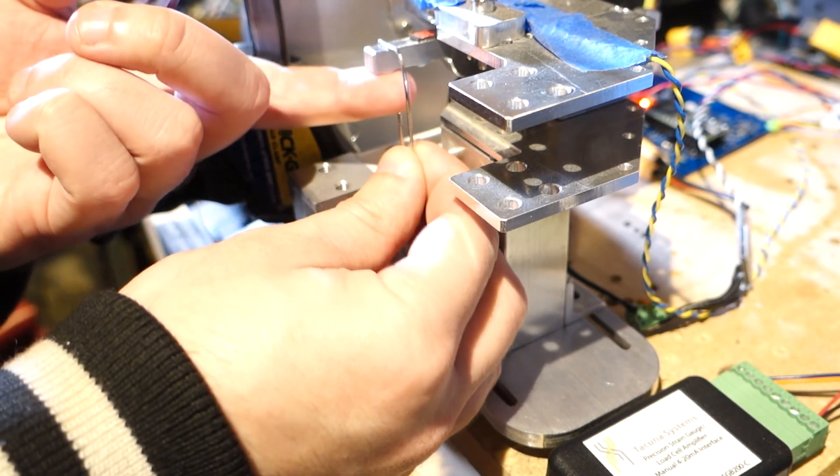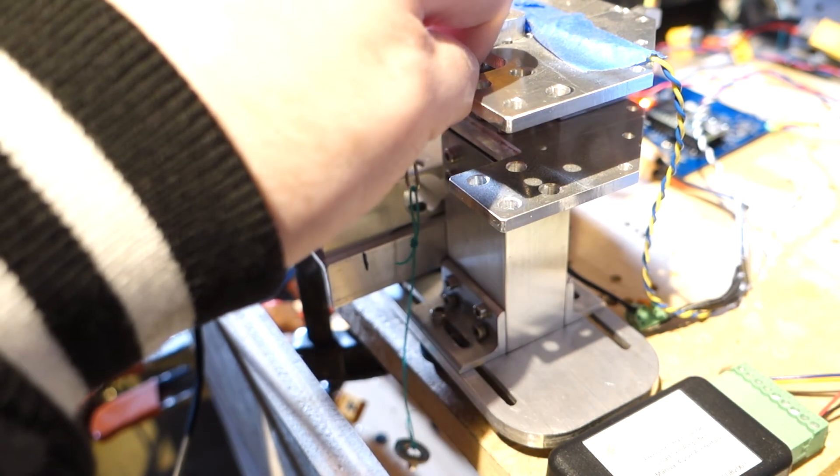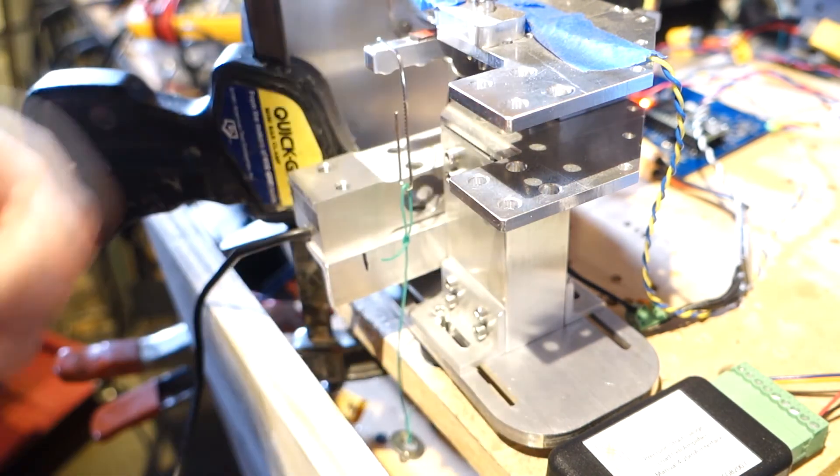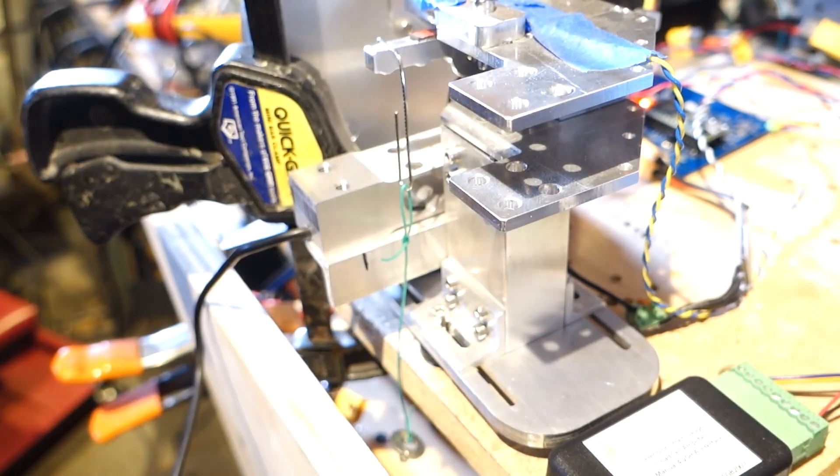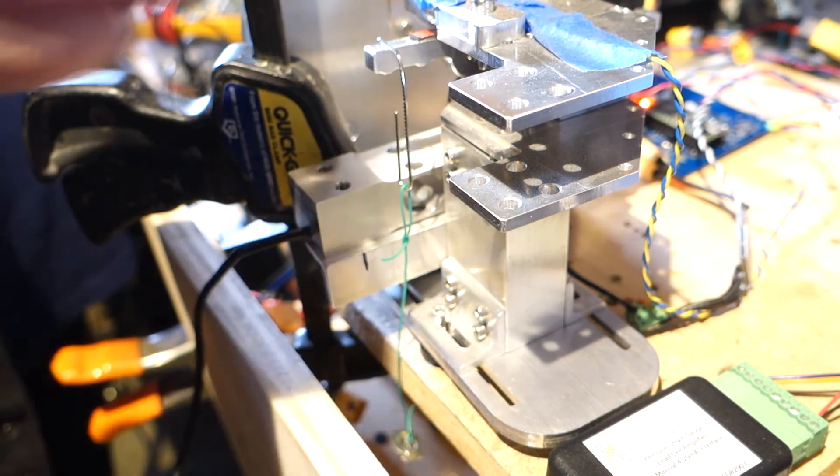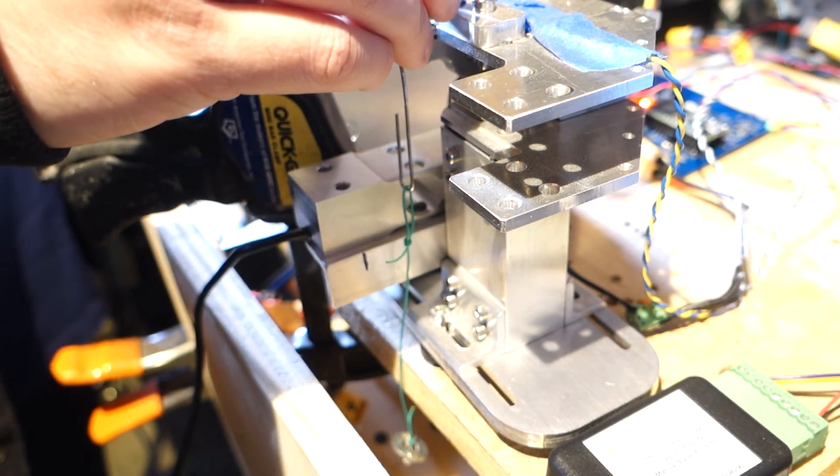The load cell calibration is a little trickier because this load cell is much larger than the stand was originally designed for, but I've got a little hanging jig that fits at a specific point along the torque arm that allows me to hang the test weights from it without interfering with anything else.